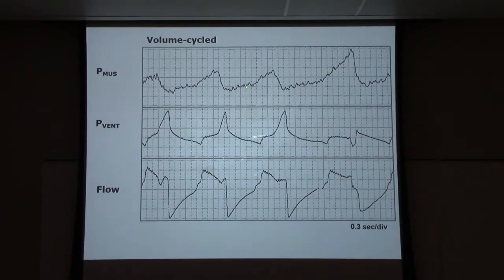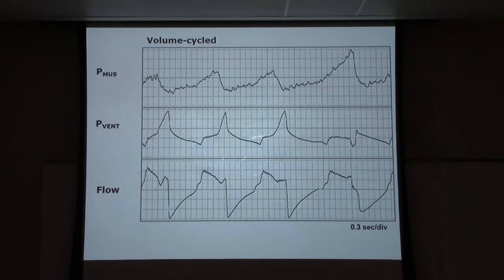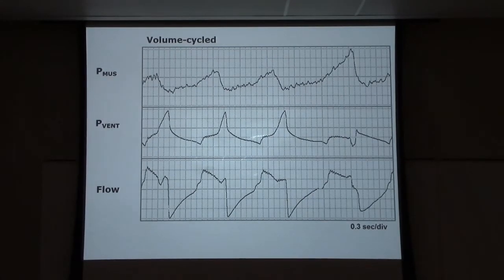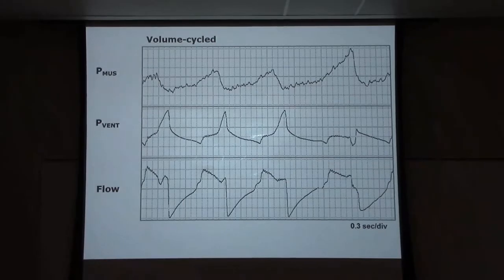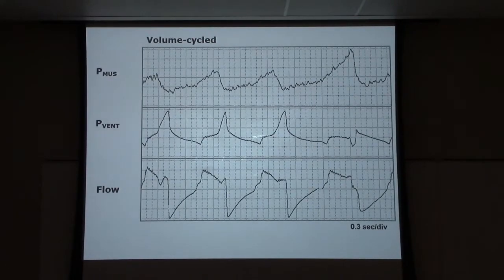So look at this. The patient is pulling here. He's not getting much assist. The assist actually comes when the patient relaxes. Why is that? Because when you have two power sources and you tell the controller, I want the same current, when one power is up, the other has to go down, right? Because the total voltage difference has to be the same. So, is that clear? This is not a bad ventilator.